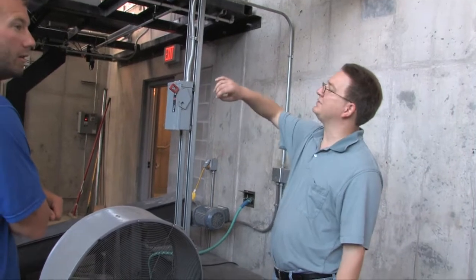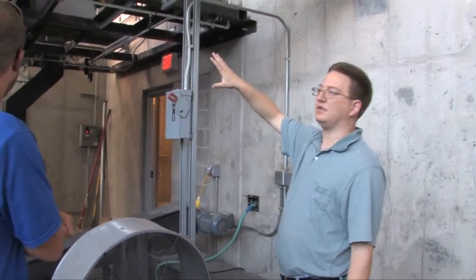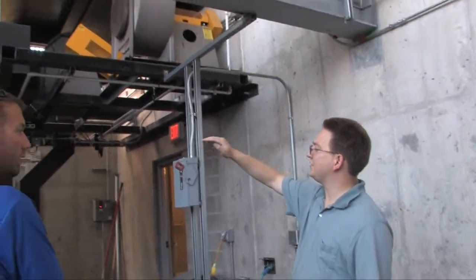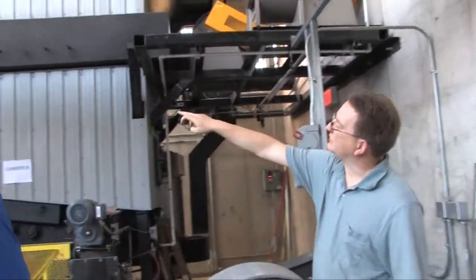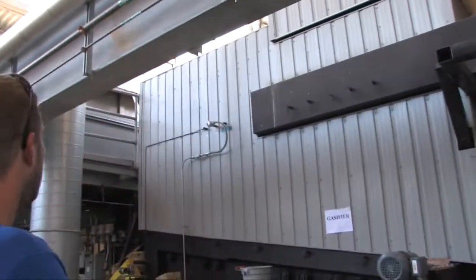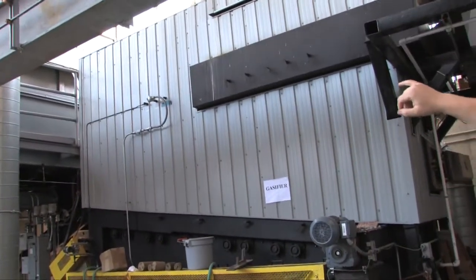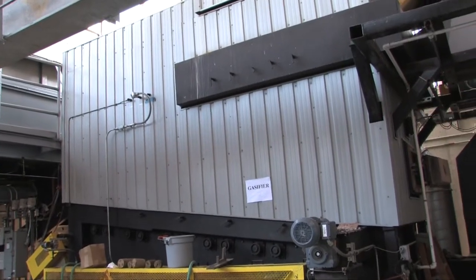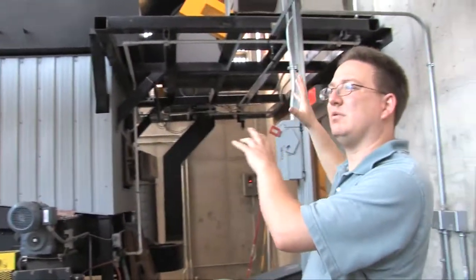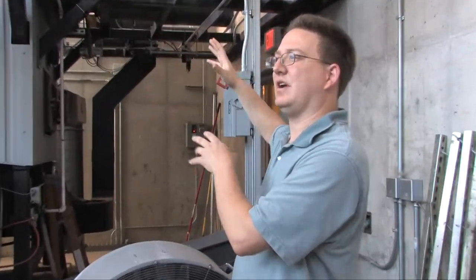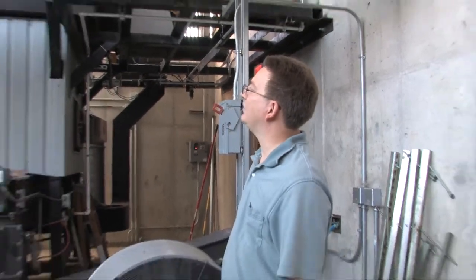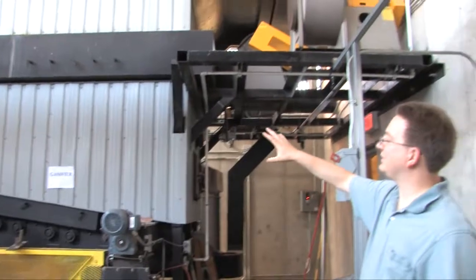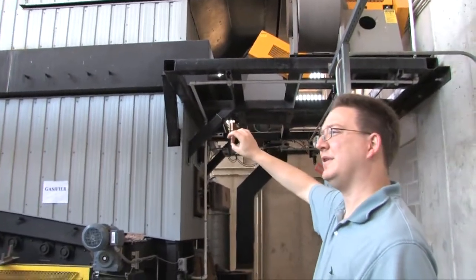You won't see it on this side as much, but since it is a research project, we do have a bunch of temperature sensors on the other side. You can see there's one up there, but on the other side there's about six more of them. So we test pressure and temperature there. And the whole system is really regulated by air flow and pressure, air pressure in there. And so in the gas chamber itself, we keep a slightly negative environment.